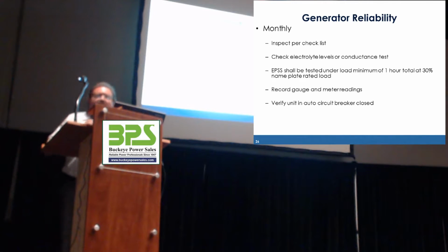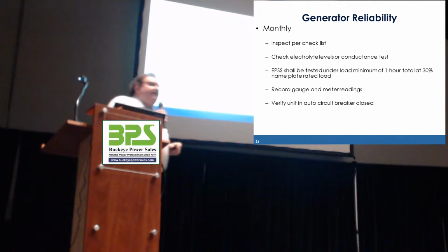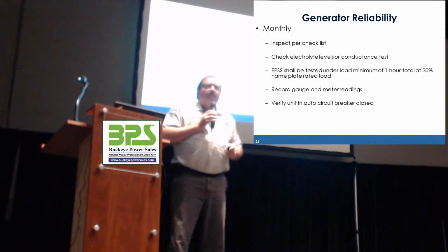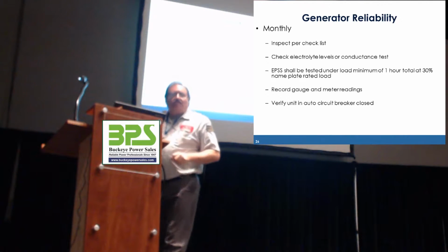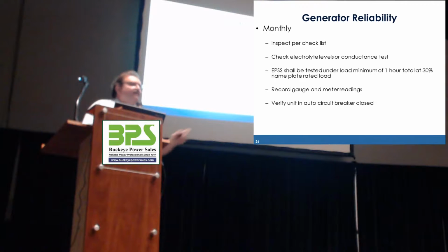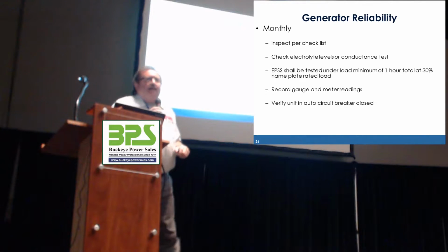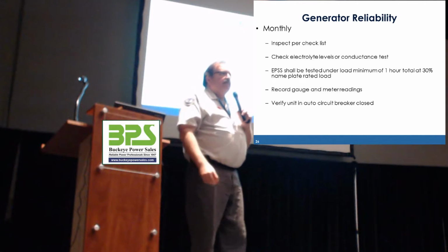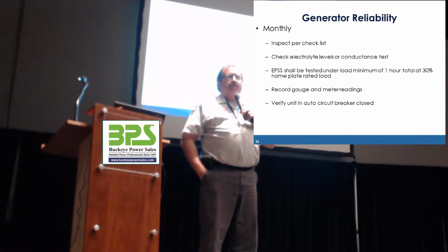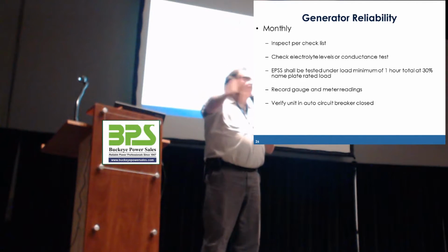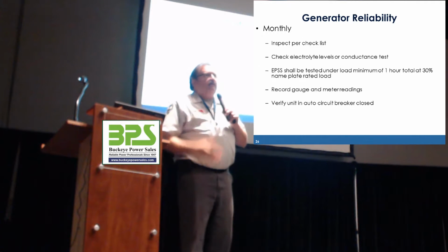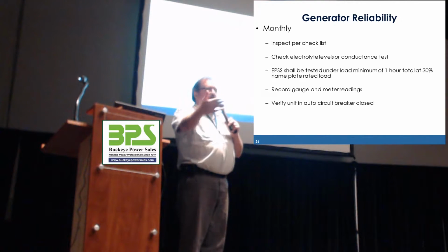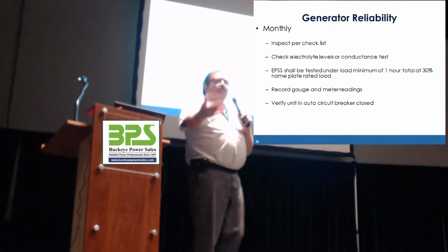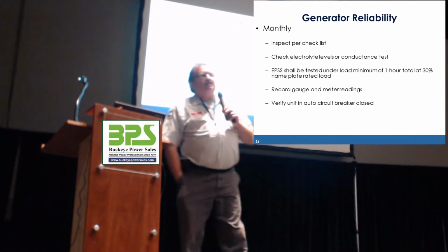I've got a data center right now that about 6 years ago put in a single generator and a single service entrance rated transfer switch. They will never permit anybody to transfer the transfer switch. So 6 years later, they had a power outage, and guess what happened? The transfer switch didn't transfer. And we have been telling them over and over again that this stuff has to be maintained. It was a breaker-based switch. It needs to be operated. It needs to be exercised, and they wouldn't do it.